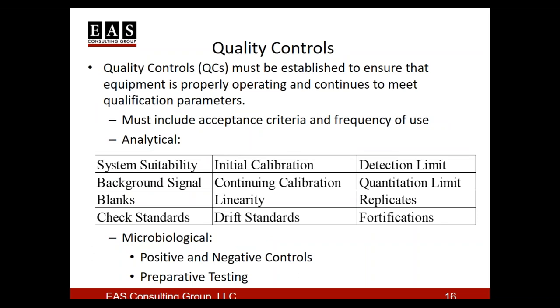Then we'll establish quality controls, or QCs, to ensure that the equipment is properly operating and continues to meet those qualification parameters. These will have acceptance criteria, a plus or minus, a percent recovery, and a defined frequency for how often we have to do this.